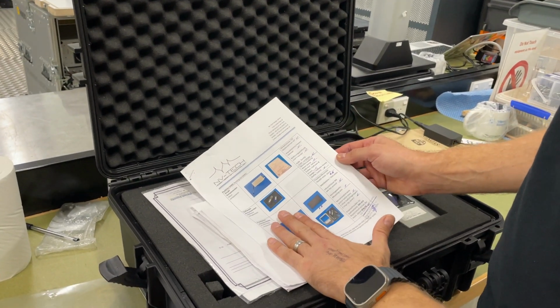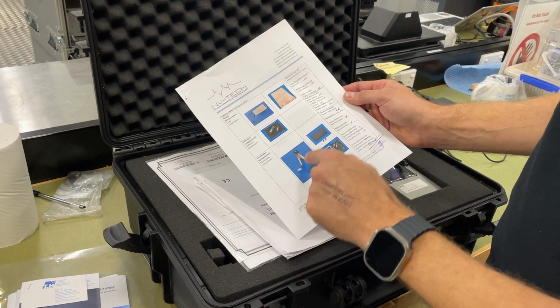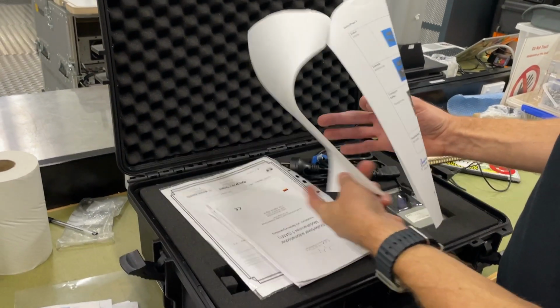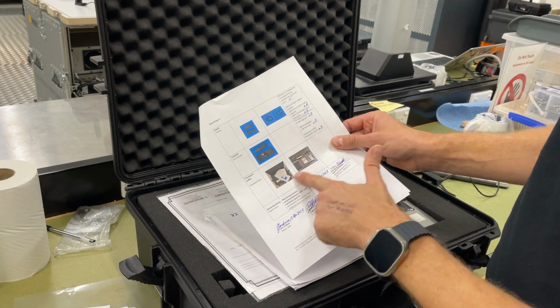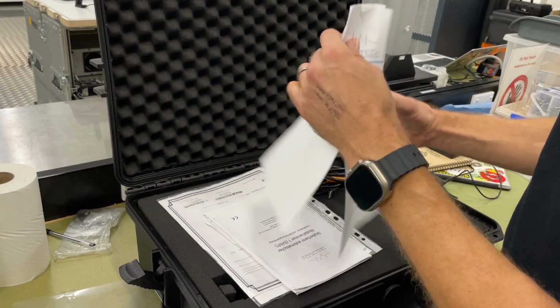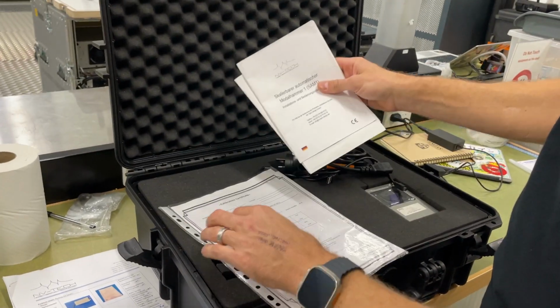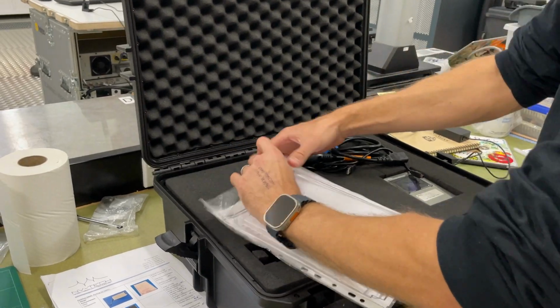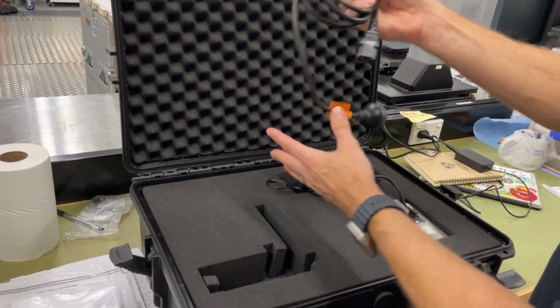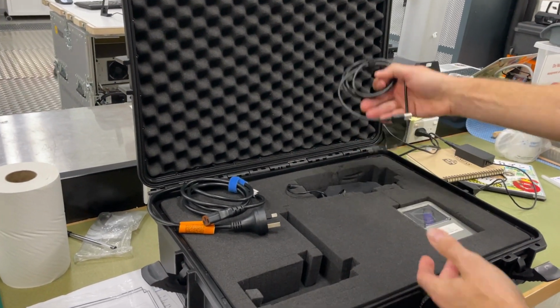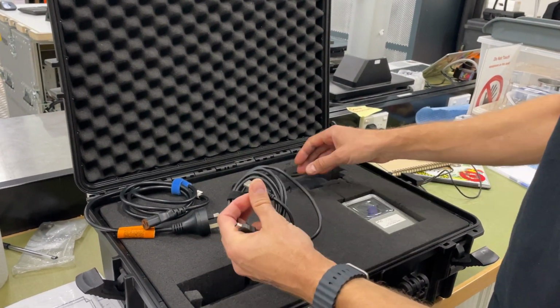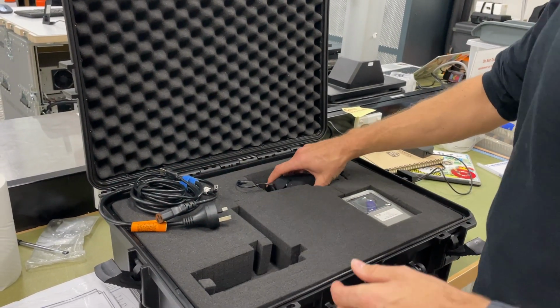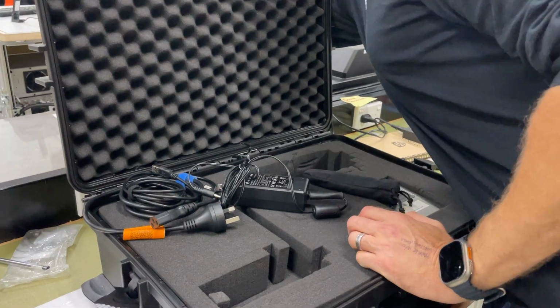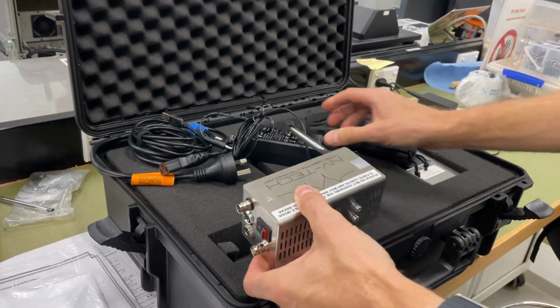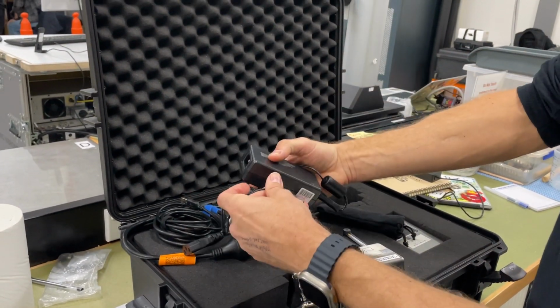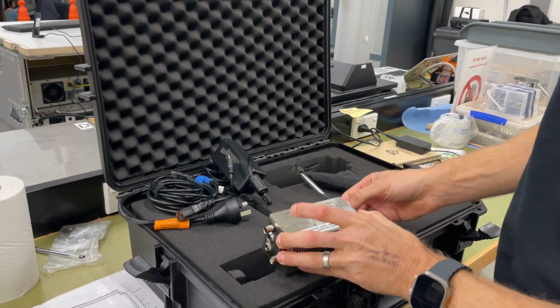We don't have this one at the moment, but we do have these holders elsewhere in the Vibration Lab, and then some cabling and some other items, and a couple of pictures showing all of the contents of the box with the automatic hammer. These are the old documents from prior to having the system upgraded. We keep those also for reference. We have a power cable, standard kettle lead as it's referred to, a USB cable which provides the communication between the modal hammer and the computer system. I just noticed that the modal hammer wasn't immediately there. There's a power supply also which provides power for the stepper motor, which is what drives the automatic hammer.